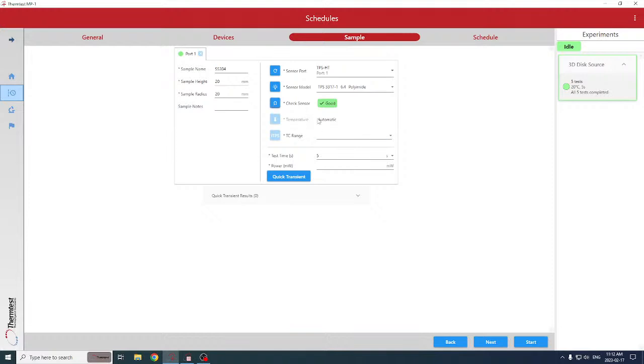So, as always, we can use the ITPS to run the parameters, which if you want to see that in previous live demos, you can. The ITPS automatically suggests the parameters for the measurements. We won't bother with that today. The temperature is automatic. It's taken from the controller itself. The parameters suggested for the measurement are 500 milliwatts, but of course you have a wide range of powers you can use. And the suggested time is 5 seconds, and that is the ideal time to keep the heat we introduce in the sample within the dimensions of the sample.